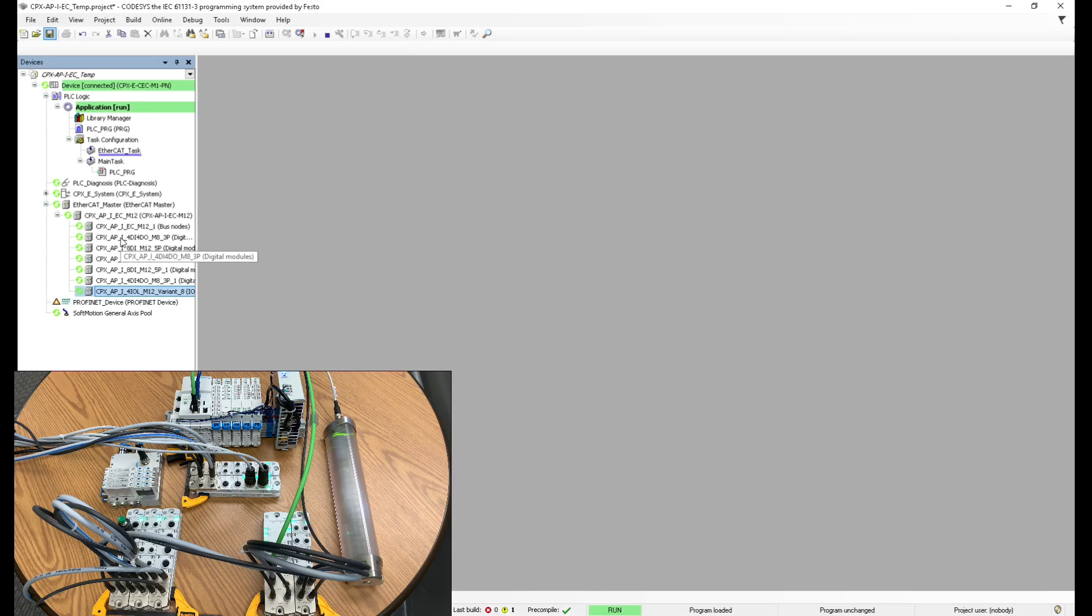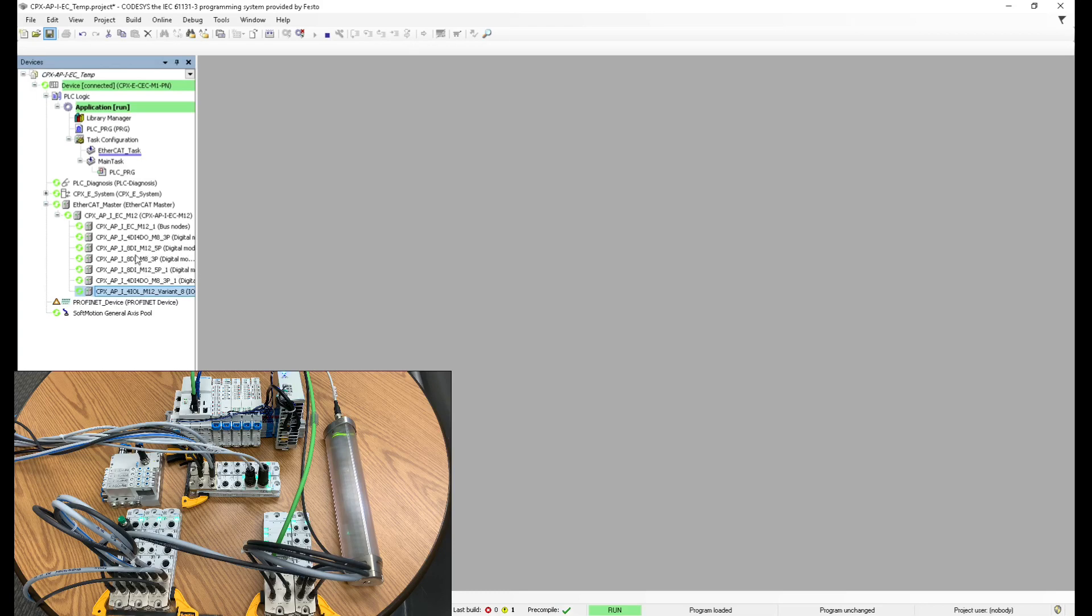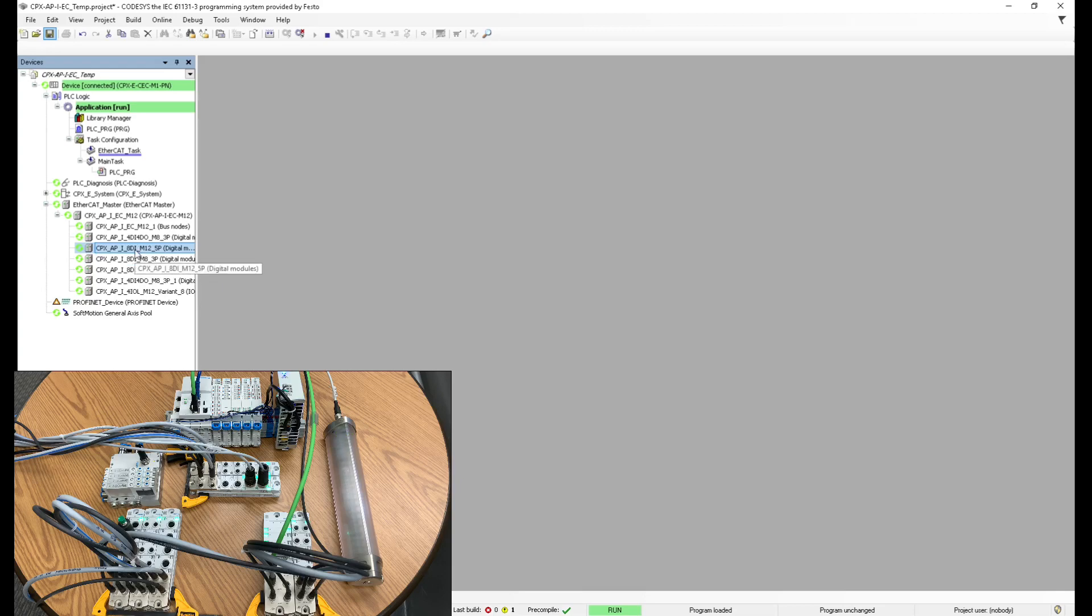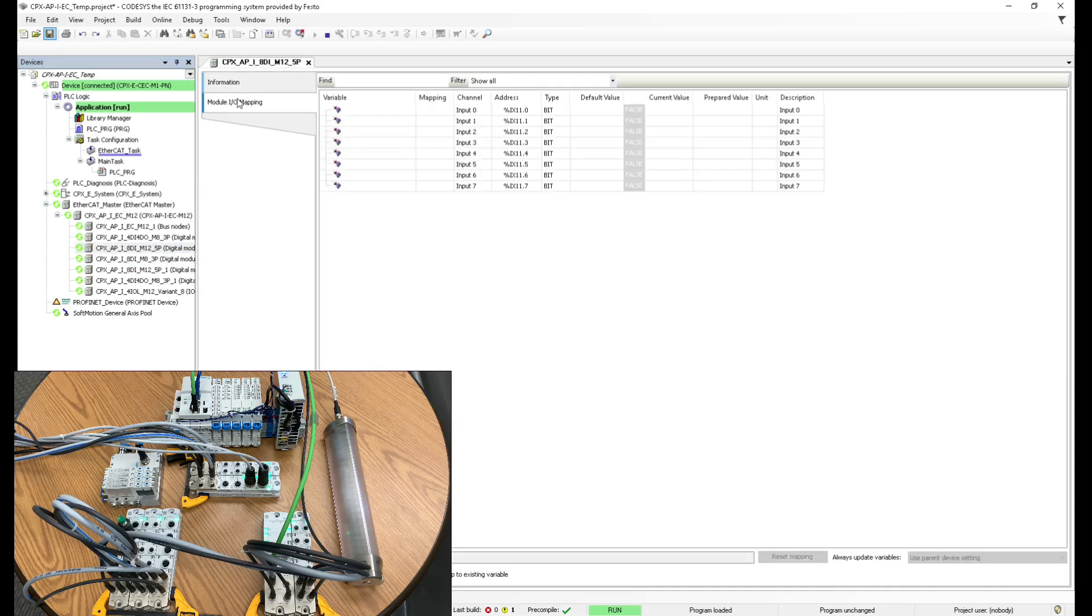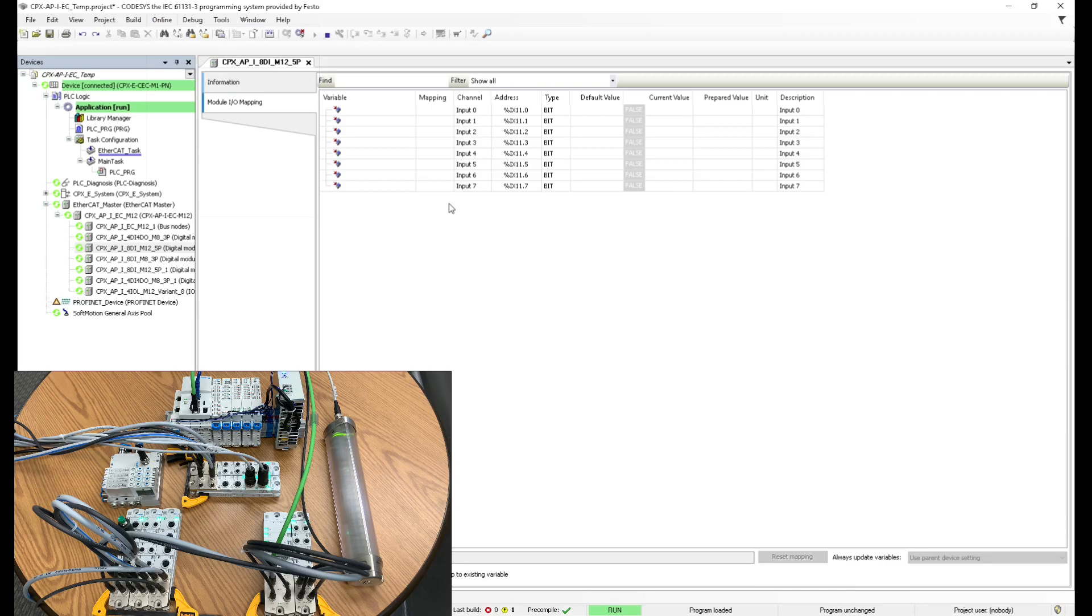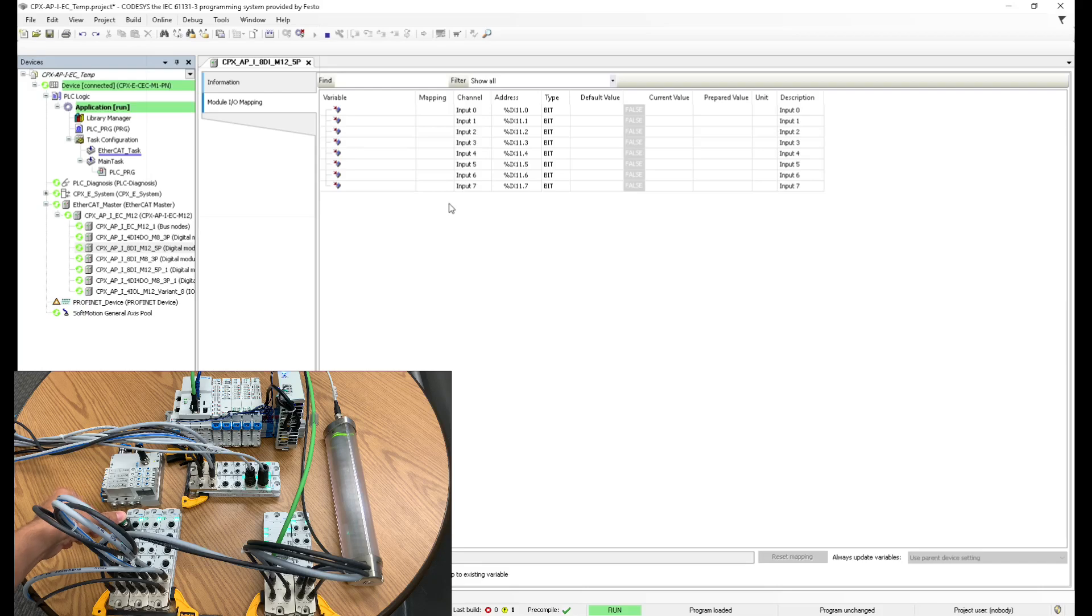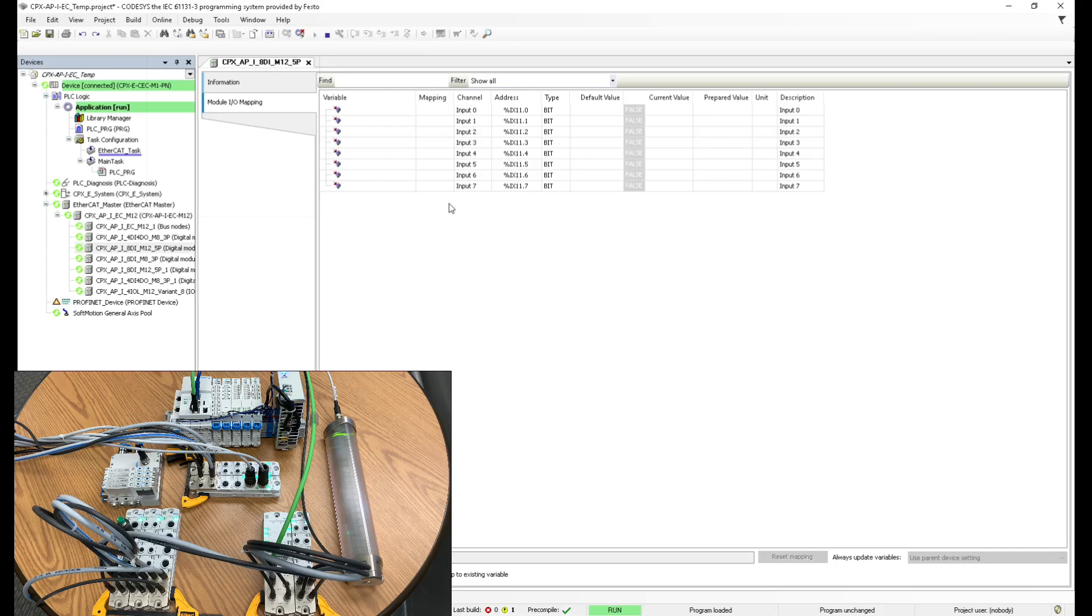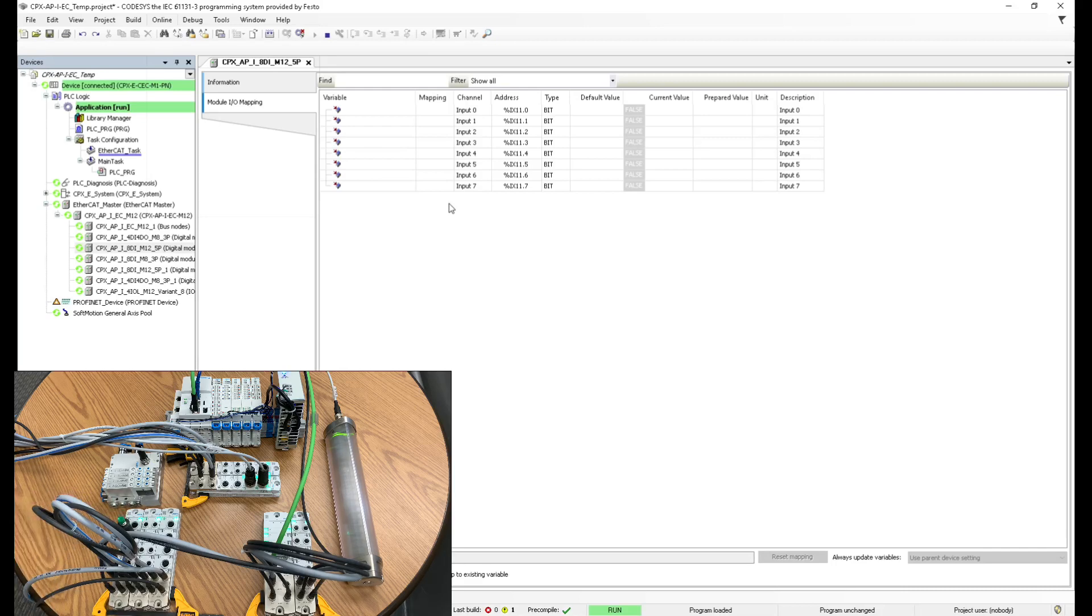Now I mentioned that I have a push button on one of the modules connected to it. That one is actually the third module. So I can see the status of that input, but first I gotta adjust something. If I press that button right now, you can see that it doesn't switch from false to true on my CODESYS project. It's not switching. Why? Because CODESYS has an option that says always update variables. And right now it's using this option. You can change it from here.